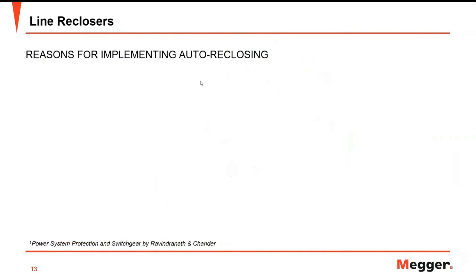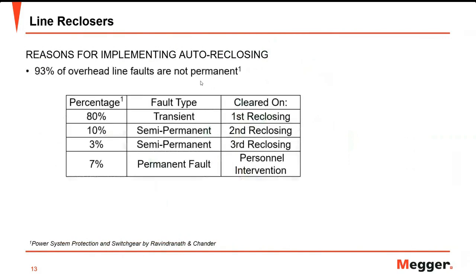Why do electric utilities implement automatic reclosing? First, because more than 90 percent of faults are transient. Transient faults can be caused by lightning or foreign objects touching the conductors. 80 percent of the time the fault is cleared on the first reclosing, yielding a successful first auto-reclosing. Some foreign objects like tree branches that fall on conductors may take additional time until they get burned away — this may happen after a second or third breaker tripping.